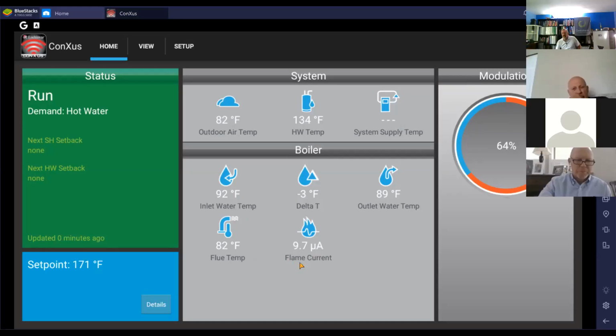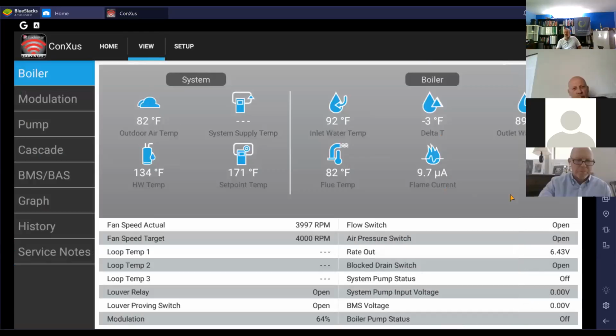Here's our flame signal, 9.7 microamps going in there. Let's jump in and see this screen right here, give you an idea where the fan speed is, where its target is, what it's at. Just real quick, so you see this here, my modulation at 64%, and that correlates to this output rate of 6.43 volts out. Those are generally going to be the same.